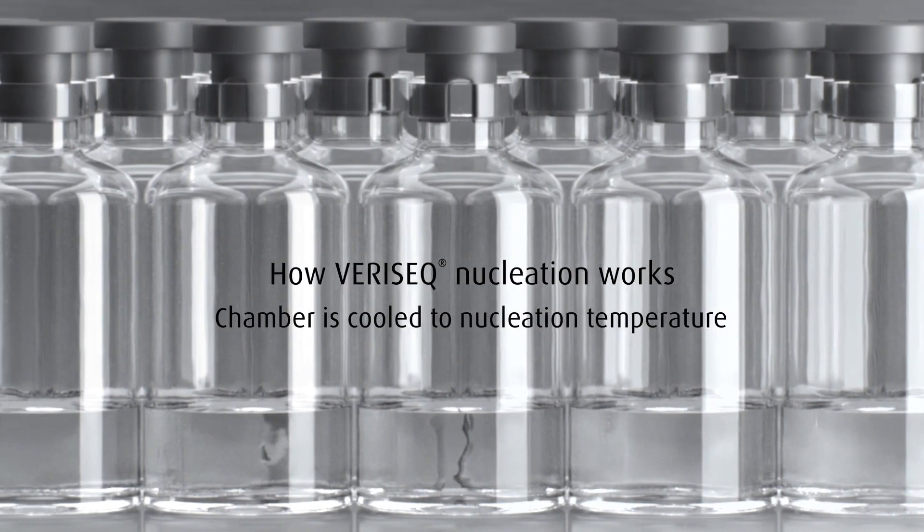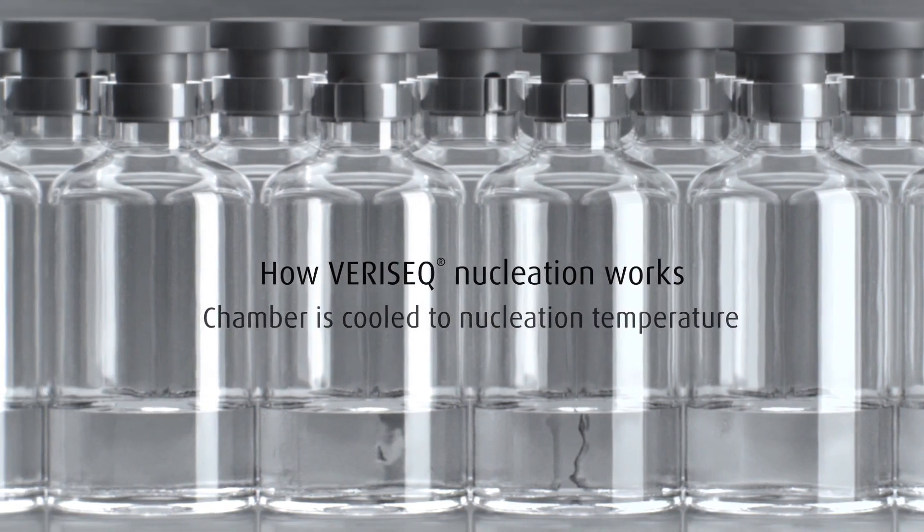Let's have a look at how VERISEQ nucleation works. The freeze drying chamber is cooled to nucleation temperature.